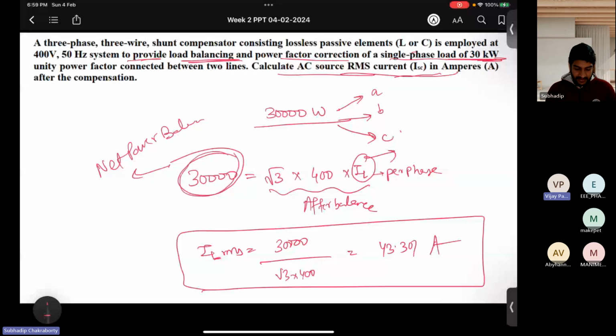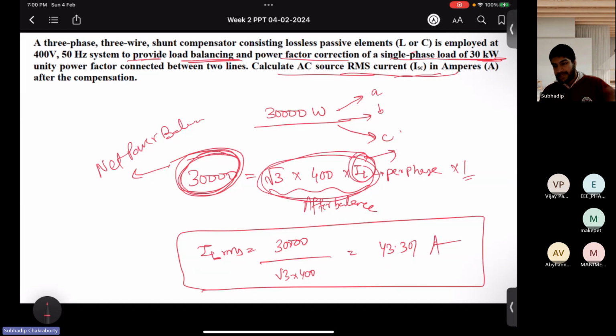So that is what I am doing, power balance. Before compensation the load was 30 kilowatts. Now, once you have provided compensation, your power factor has gone to unity for all the 3 phases. And why do we do load balancing? I told you, to split the power among the 3 phases equally. So 3-phase power at unity power factor is √3 VL IL cos phi, and cos phi is 1. Now, what will be the current of all the 3 phases after compensation, that is, after balancing the load? Then we are calculating the current.